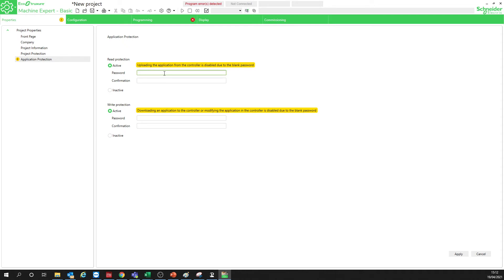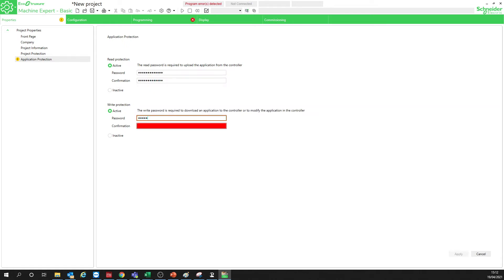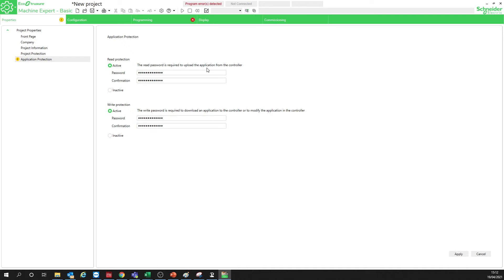So we can write something here — for example, entering a username and password like 'Administrator'. You can see we now have different notifications. So if you want to read from the controller, when you download this it will ask you for a password. And if you want to download a new application — the write protection — you will need to log in to the controller using this password. You can have different passwords for read and for write.